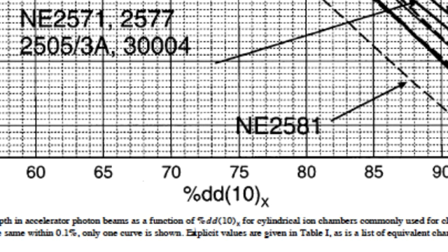One thing I'd like to talk about a little bit is this PDD. So it's percent depth dose measured at a depth of 10 centimeters in water, and then it's got the little symbol X next to it. You see that? So what that means is that you're looking at the X-ray component. So you want to filter out the electrons that come from the head, and that's especially important for high energy beams above about 10 MV, because those contribute lots of electrons at shallow depths.